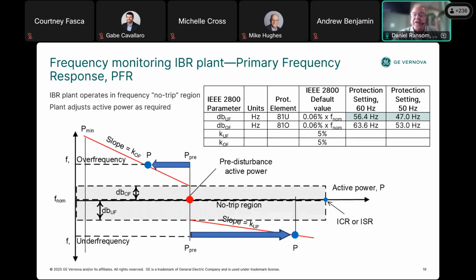The plant adjusts active power as required during and after a frequency excursion defined by the deadbands with fast underfrequency elements, 81U, that I just discussed. This helps the grid frequency recover and be stable. The IBR injects power based on the departure from the frequency, and that's in a frequency deadband dB under frequency, dB UF, and dB OF, dB over frequency. And these are at the droop rates of KUF and KOF for under frequency and over frequency deviations, respectively. Here's an under frequency case. The IBR maintains the power output, P pre, while the system frequency is dropping. At the end of the under frequency deadband, the IBR increases power to the new operating point, and this furthers stability in the grid.